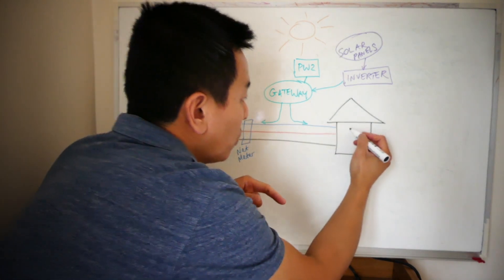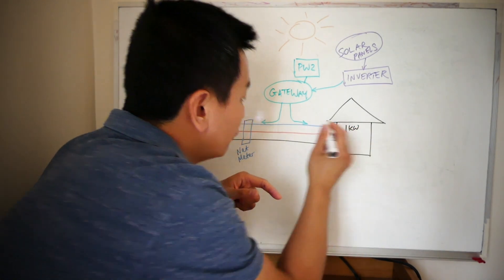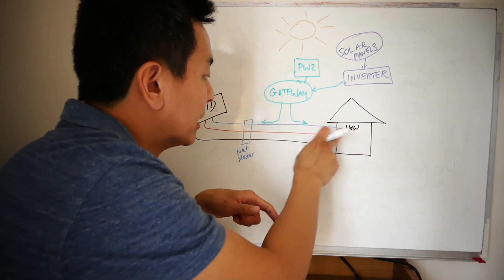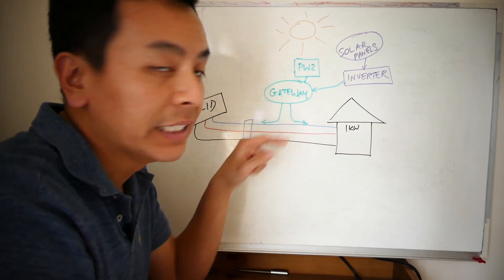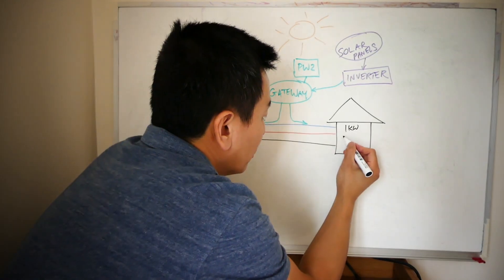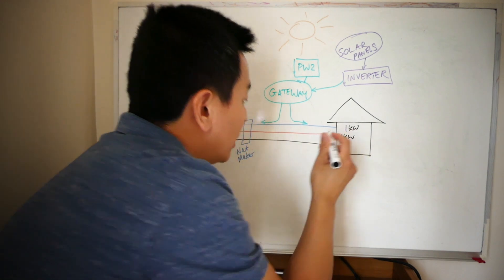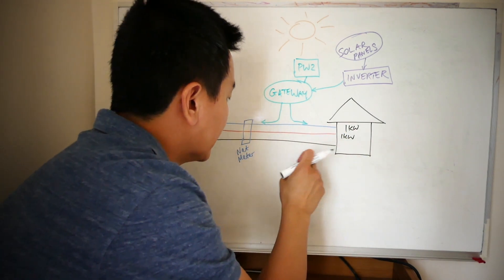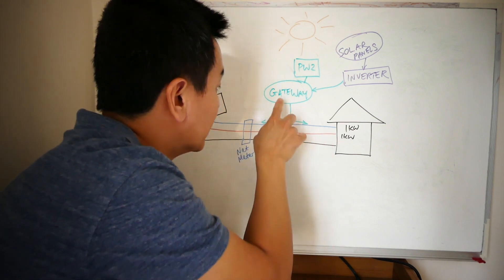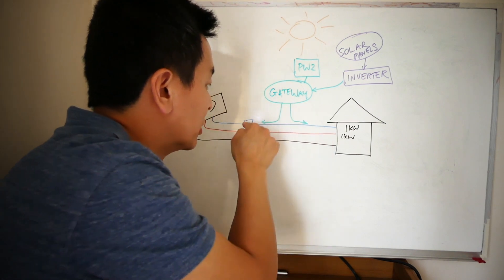If there is a one kilowatt load here on the blue phase, the gateway will happily supply the home on this phase here. If there is a load here on this red phase, what the gateway does is allows the grid to come in with the red phase, but then discharges one kilowatt back here on its own phase.